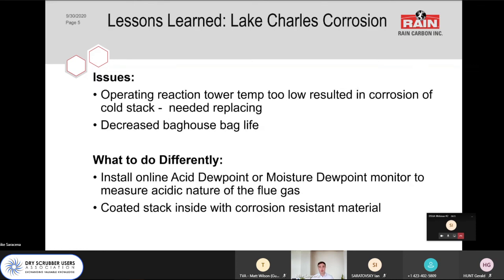So getting into some of our lessons learned, immediately upon commissioning and probably for a few years after at Lake Charles, we had some fairly severe corrosion issues. Basically, the root cause was our operating reaction tower temperature was too low and either too close to the acid dew point or below the acid dew point, which resulted in some severe corrosion of our cold stack. So a few years after we commissioned, our entire cold stack needed to be replaced. And we also had decreased baghouse bag life. We didn't really see any severe duct corrosion. It was primarily focused on these two pieces of equipment.